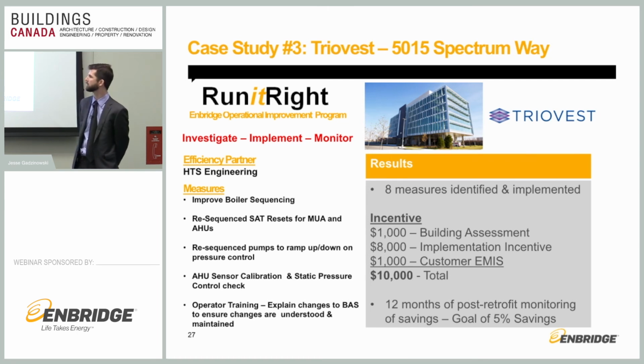AHU sensor calibration and static pressure, just checking the pressure sensors in the ducts, making sure that they're calibrated correctly. And then they also trained the operators. They explained all the changes to the BAS that they made and ensured that those changes would be maintained over time. So there was some money for operator training there as well.